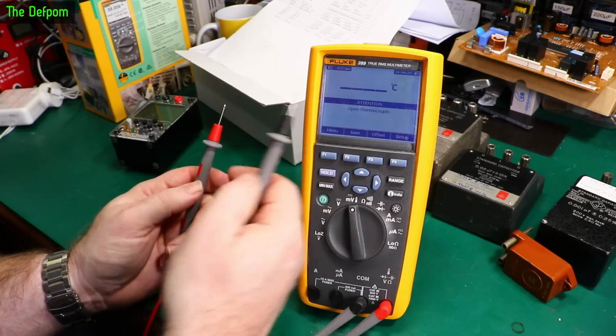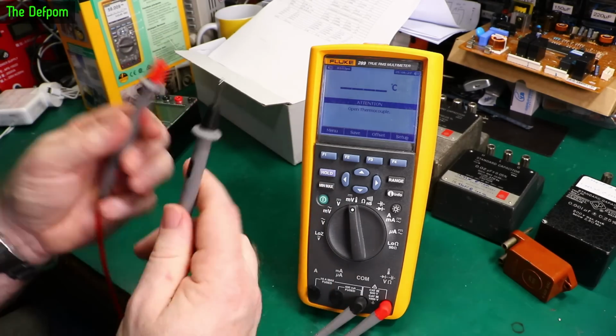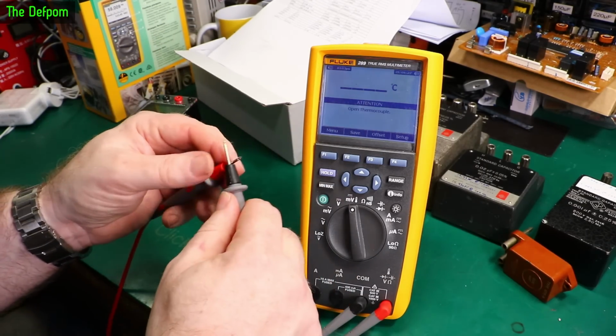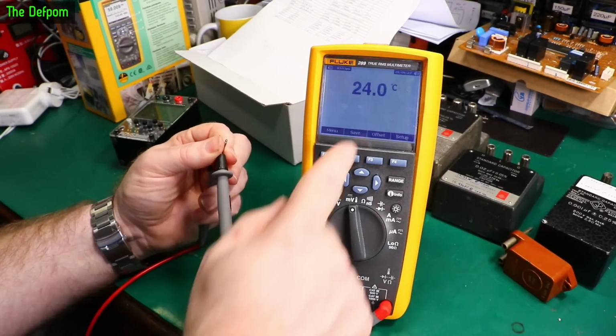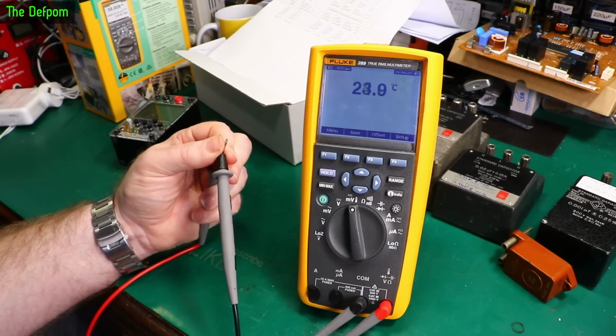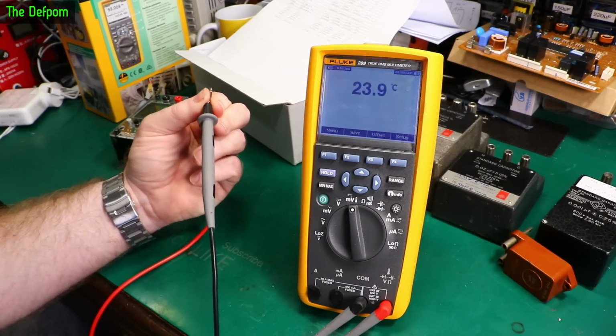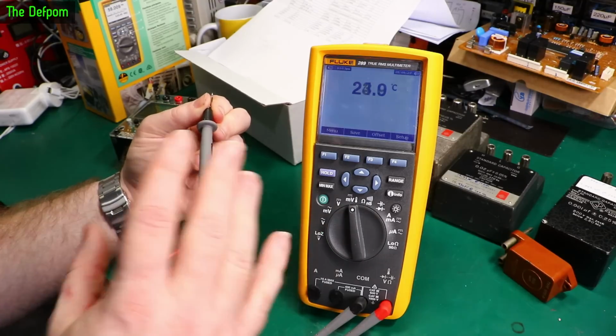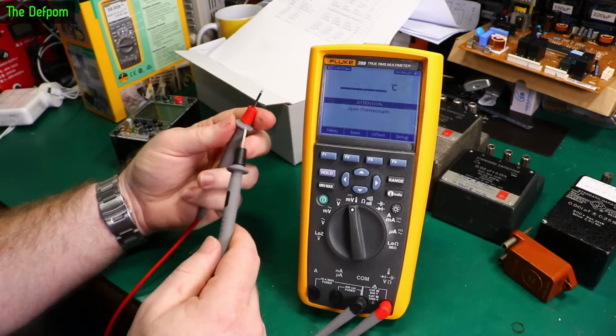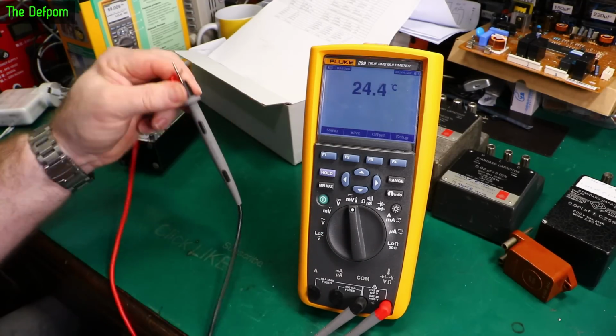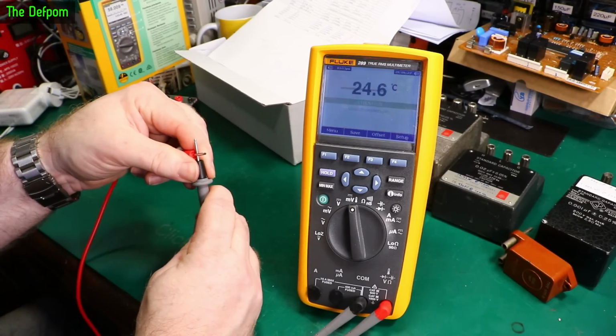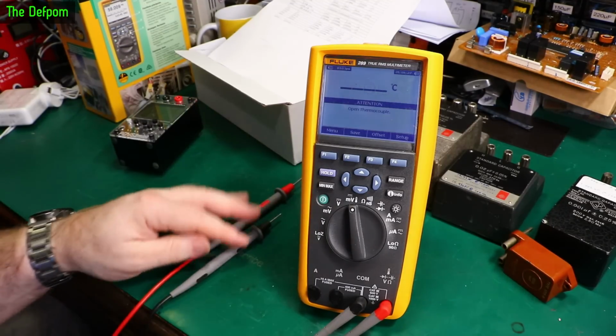And right now it's showing open thermocouple because I don't have a thermocouple plugged in. But I'll show you something. Short little leads together. These meters show temperature, 24 degrees, because they have a thermocouple built in as well, which gives it a reference point. So you stick the leads together, you actually get a temperature. Maybe you didn't know that.